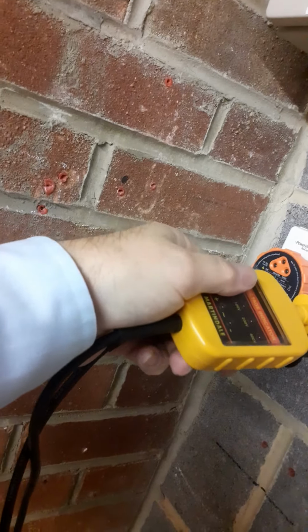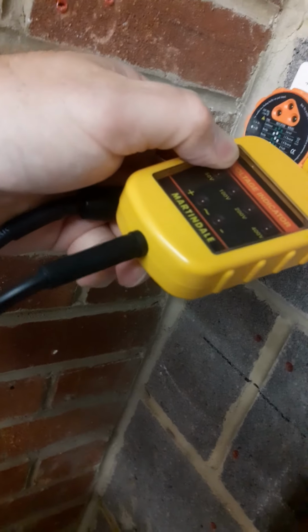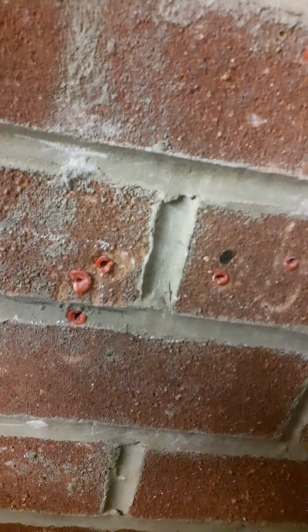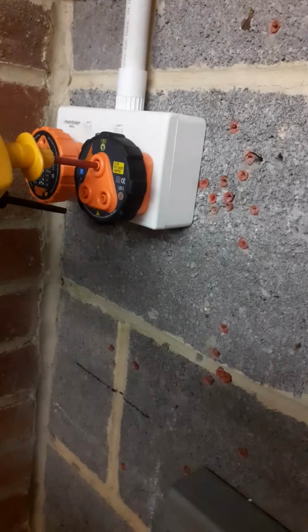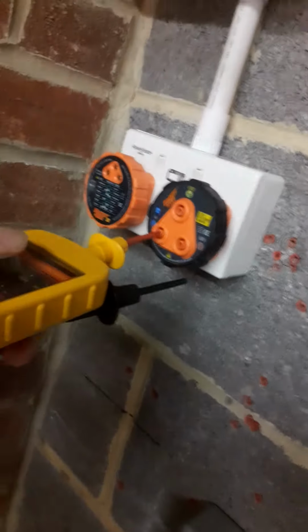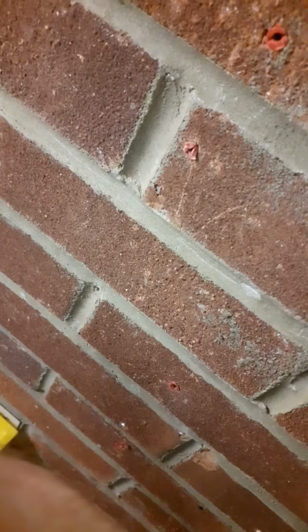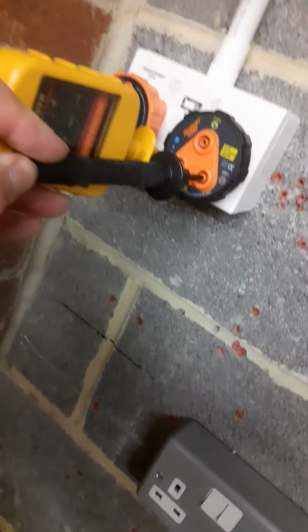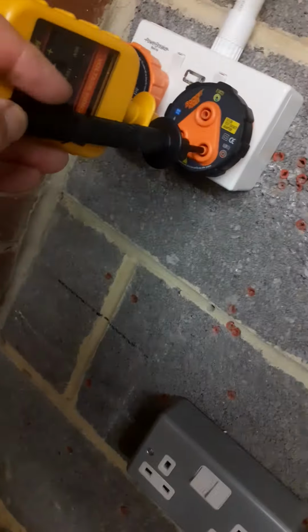Test 2, insert the probes between earth and live, and finally insert the probes between live and neutral. What you never do is insert the probe in the live conductor on its own. So you do earth to neutral, earth to live, neutral to live. That proves the circuit is dead, but the voltage indicator could still be broken. So the last check is to reprove the voltage indicator. Then we know the circuit is definitely safe to work on.